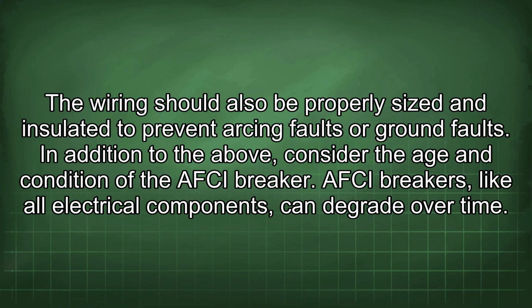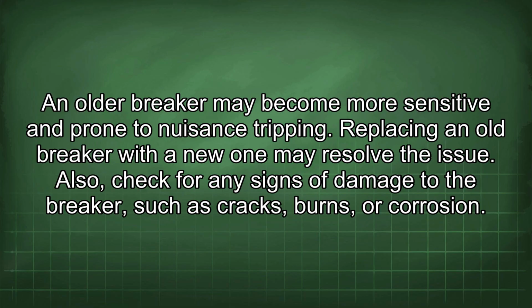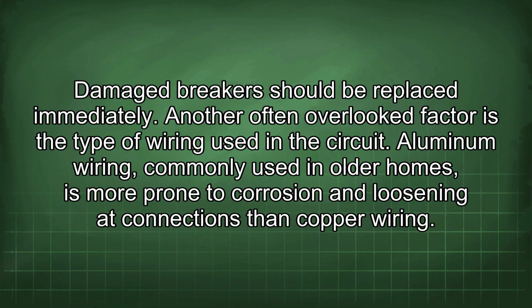In addition to the above, consider the age and condition of the AFCI breaker. AFCI breakers, like all electrical components, can degrade over time. An older breaker may become more sensitive and prone to nuisance tripping. Replacing an old breaker with a new one may resolve the issue. Also, check for any signs of damage to the breaker, such as cracks, burns, or corrosion. Damaged breakers should be replaced immediately.